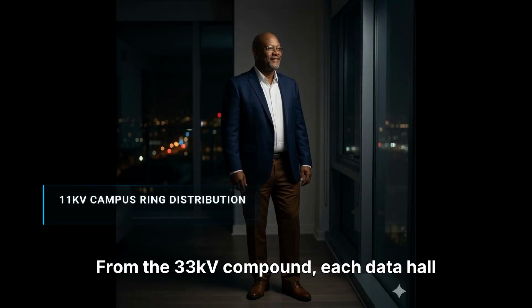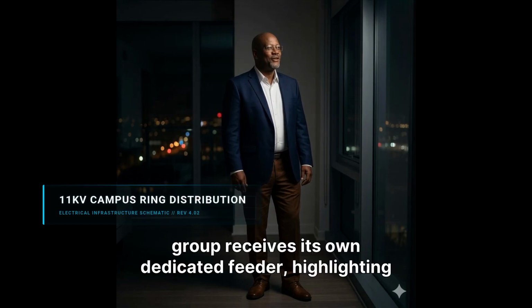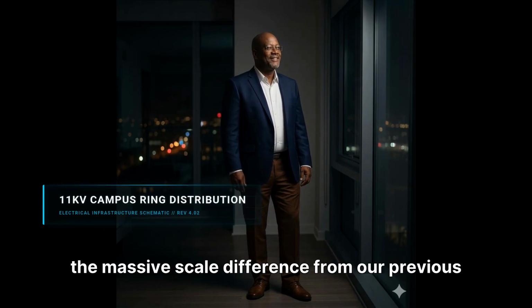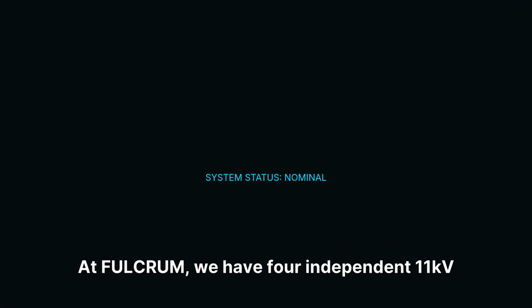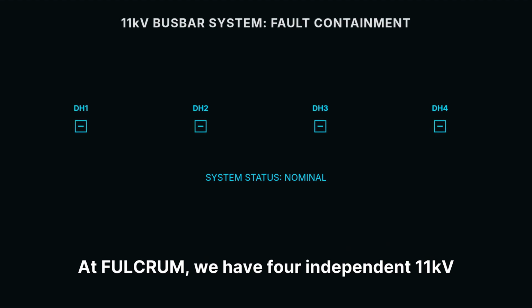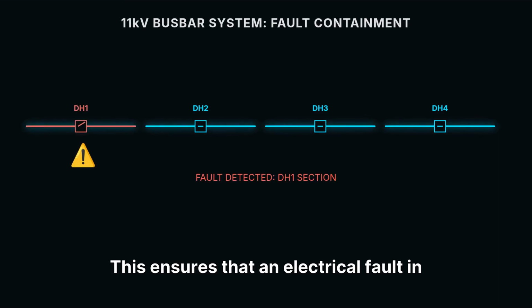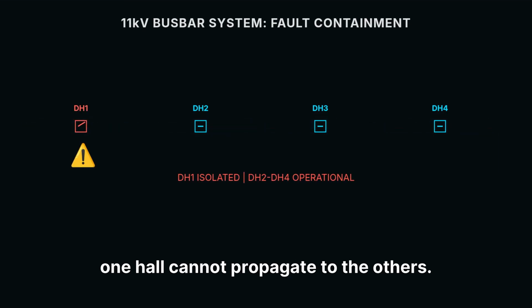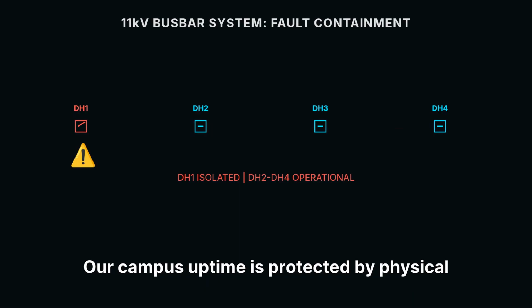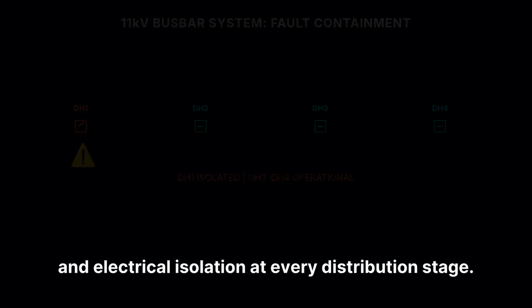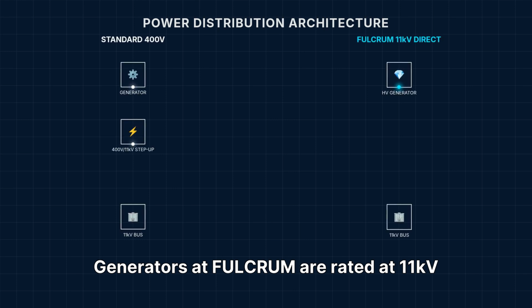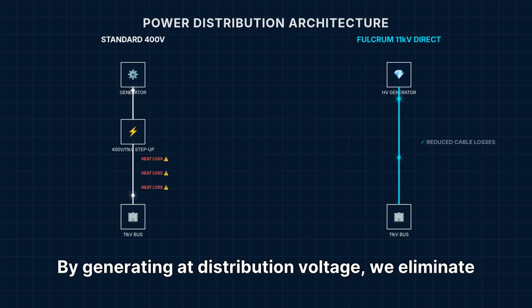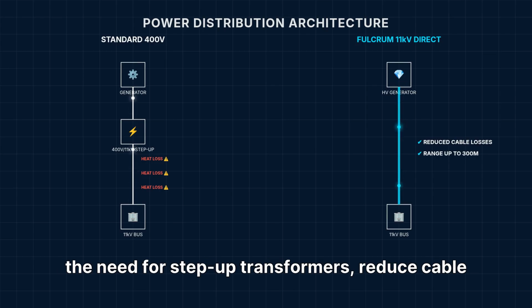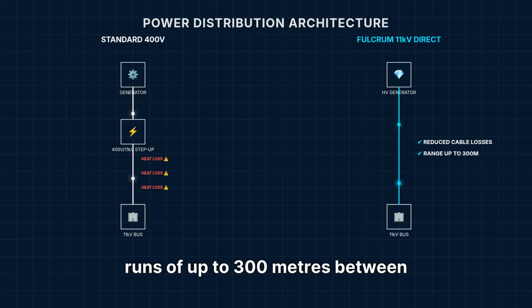From the 33 kV compound, each data hall group receives its own dedicated feeder, highlighting the massive scale difference from our previous projects. At FULCRUM, we have 4 independent 11 kV bus bars. This ensures that an electrical fault in one hall cannot propagate to the others. Our campus uptime is protected by physical and electrical isolation at every distribution stage. Generators at FULCRUM are rated at 11 kV output. By generating at distribution voltage, we eliminate the need for step-up transformers, reduce cable losses, and allow for much longer cable runs of up to 300 meters between the yard and the halls.